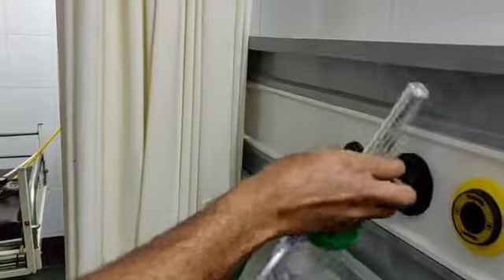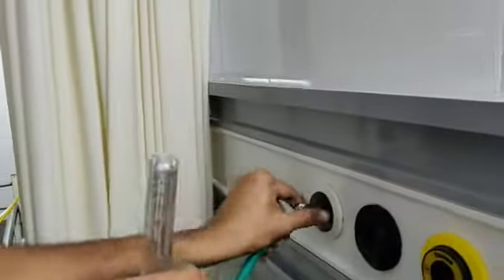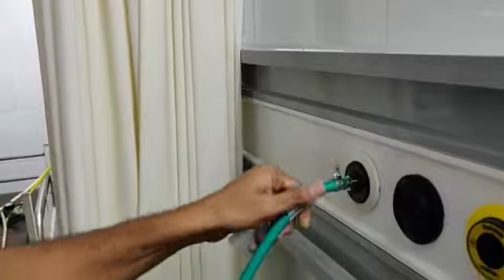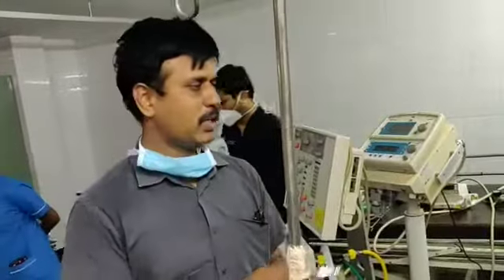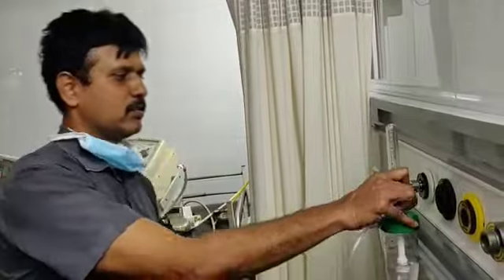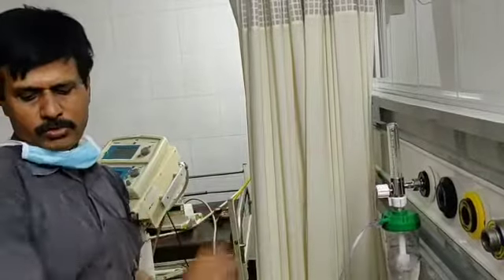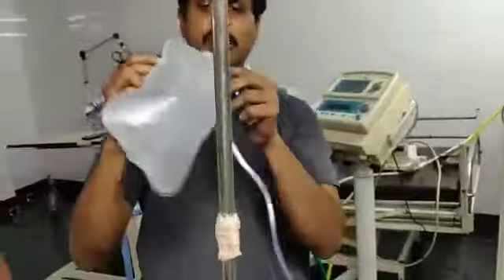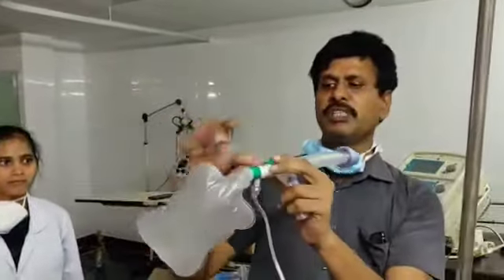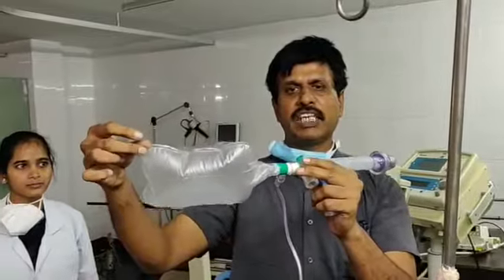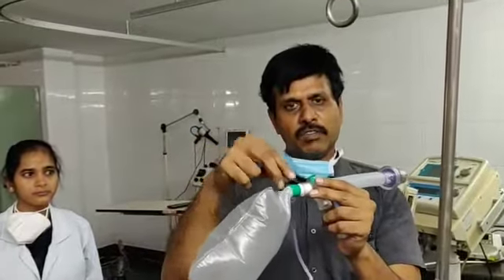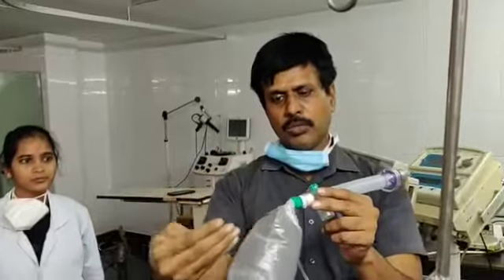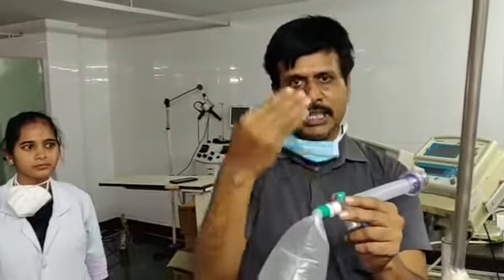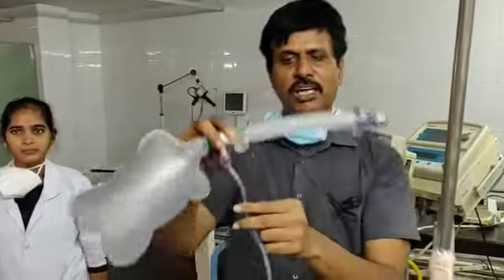So connect to the oxygen. Connecting to oxygen, making it 15 liter flow. And what I have done here, I have attached to one end of the T-piece the reservoir bag, which has a valve that allows only one way. The O2 from here can go inside, but the exhaled air cannot come outside. And the oxygen is connected here.